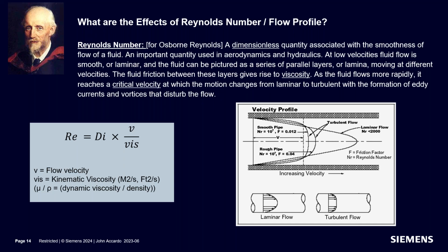So switching gears, Reynolds number is another impact that all flow meters have to deal with. Reynolds numbers determine the flow profile of the fluid traveling down the pipe. Basically, Reynolds number was developed by Osborne Reynolds, and it's based upon the dimensions of the pipe and the fluid viscosity, what shape the fluid takes on as it travels down the pipe wall. And it actually impacts the correction factor that the flow meters need to apply in order to maintain an accurate measurement.